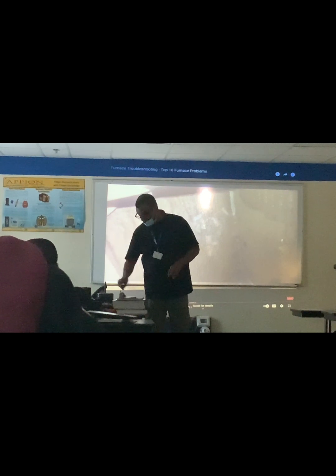So temperature. If I don't get airflow, that's temperature. The temperature safety says, hey, I'm going to open up the circuit so we don't tear up the equipment. Safety circuits in series, either in heating or cooling, are put into place to save the equipment. But if you keep running it, you can cause a limit like this to open permanently because it is cycling. We call it cycling off the limit. Since it's an automatic reset, it heats up, opens the switch, the system goes off, and when it cools off, it closes again. It keeps doing that and cycles off the system.